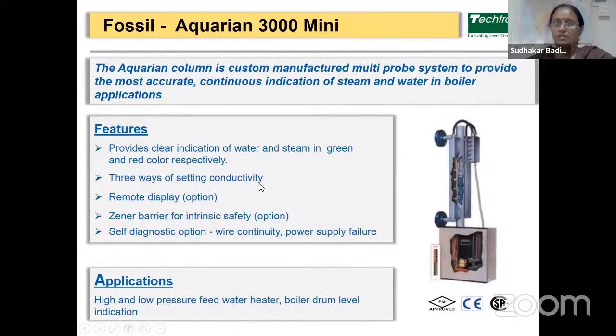So this is the upgraded one, that is Aquarian 3000 mini. This is a custom manufactured multi-probe system to provide most accurate and continuous indication of steam and water in boiler applications. So here you will get multiple probe options up to 24 numbers. It provides clear indication of water and steam in green and red color respectively. Then again, conductivity can be set in three ways. The remote display options are available.